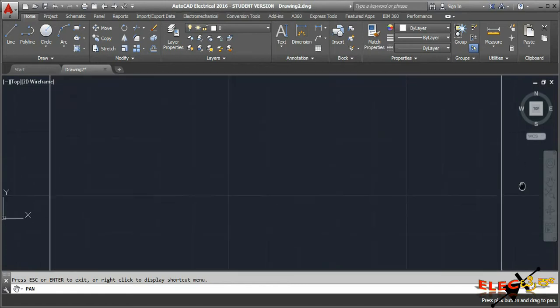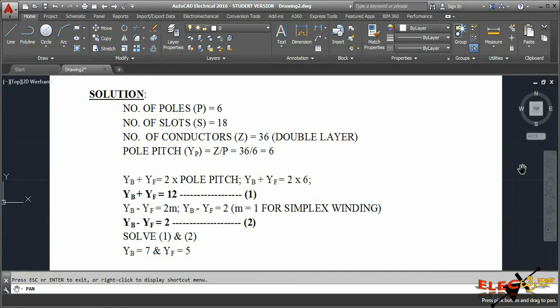The data for this problem: number of poles is six, number of slots is 18. Due to the double layer, the number of conductors will be double the number of slots, because in each slot we place two conductors - one on the top layer and one on the bottom layer. The top layer conductor is represented as a continuous line and the bottom layer conductor as a dashed line. Top layer conductors get all the odd numbers and bottom layer conductors get the even numbers.